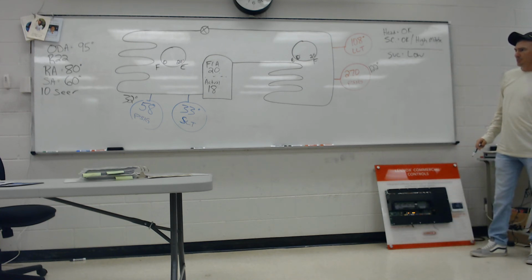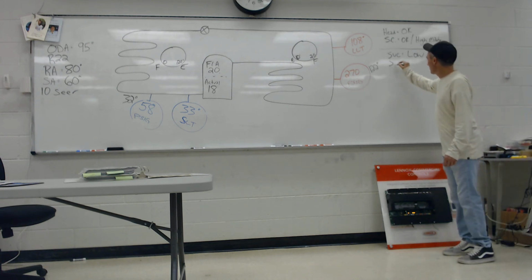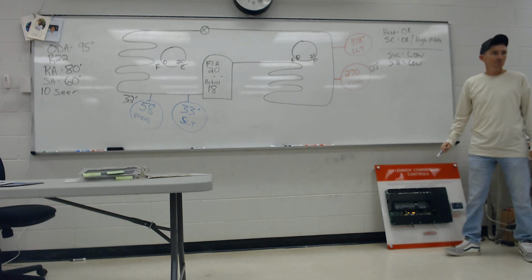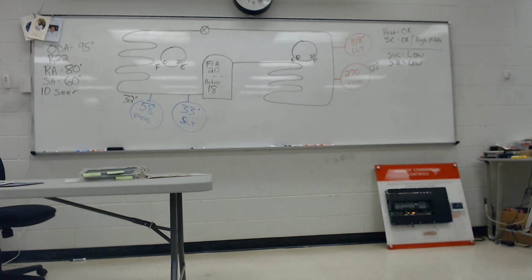Now, what's my superheat look like? 1 degree. 1 degree? Yeah. So superheat is low. Game over. I know what's wrong with it. Every time, low suction and low superheat are always airflow.